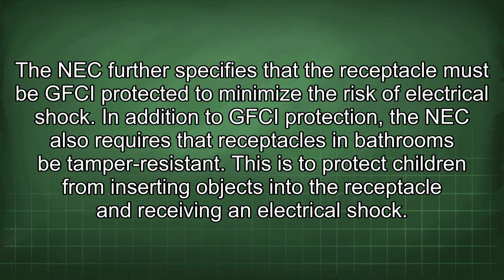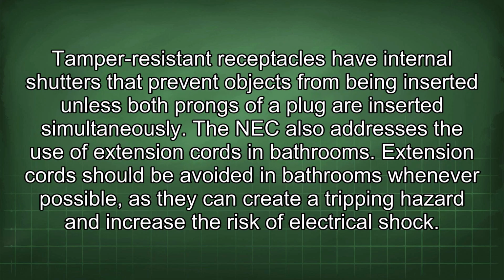shock. In addition to GFCI protection, the NEC also requires that receptacles in bathrooms be tamper-resistant. This is to protect children from inserting objects into the receptacle and receiving an electrical shock. Tamper-resistant receptacles have internal shutters that prevent objects from being inserted unless both prongs of a plug are inserted simultaneously. The NEC also addresses the use of extension cords in bathrooms.